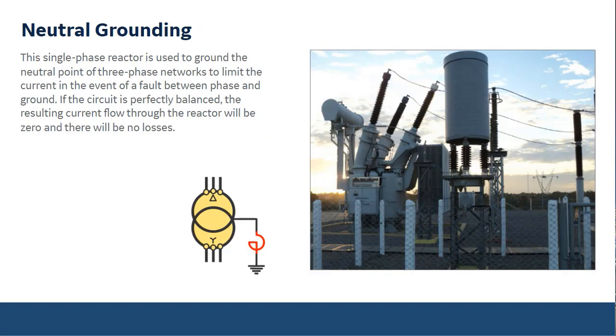And lastly, the neutral grounding reactor, which is basically a fault current limiting reactor, but in this case it's installed in the neutral of a power transformer. Most of the faults are phase to ground, so it makes sense to have an impedance placed on the ground of the transformer, to limit, again, the fault current of the system.